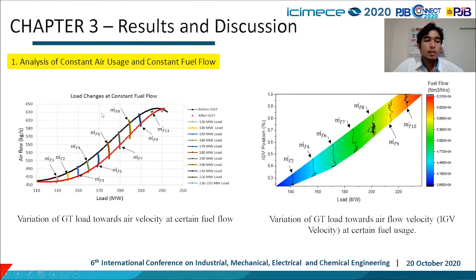As a comparison, the variation of airflow in a specific fuel consumption is also observed, as shown in this figure. This figure shows the details of this research. In a constant fuel flow of 10.6 kg per second, the air flow is varied so that the optimum load of gas turbine is obtained at 150 megawatts. This value becomes the new IGV opening point or optimum operating point. These optimum operating points are compared with every constant fuel flow to produce the curve of IGV opening position after IGVT implementation.